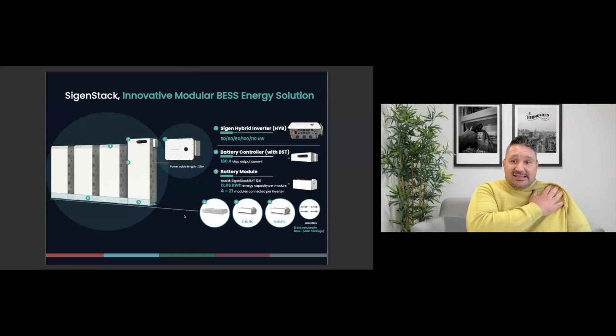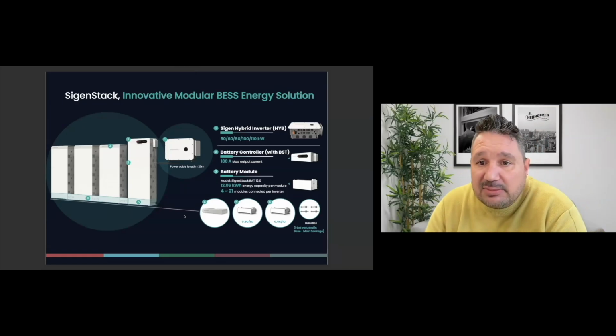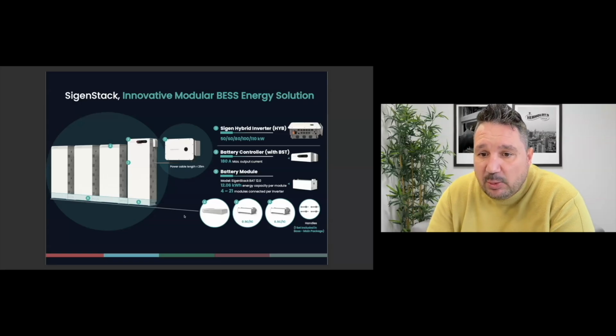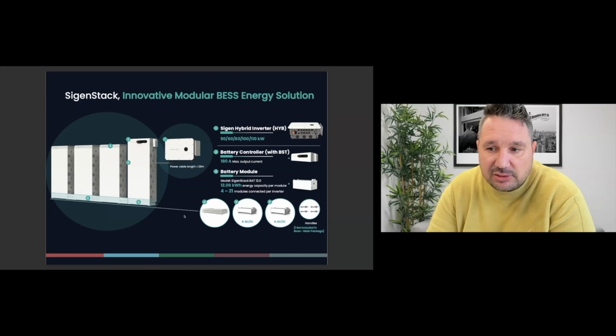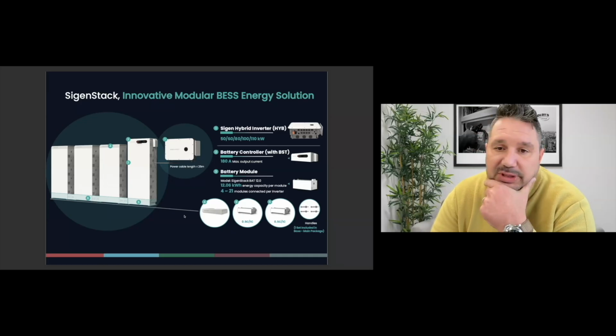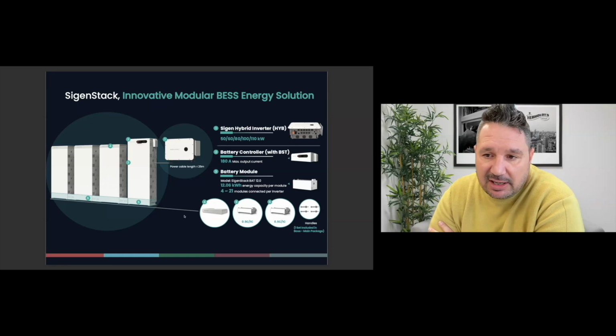SigenStack, which is the C&I and industrial solution, now comes between a 50, 60, 80, 100, and 110 kilowatt hybrid inverter with a battery stack that can stack up to 240 kilowatt hours per unit, which can give you a 1C or half C type design. Each one of these battery modules is 12 kilowatt hours. They stack on top of each other and then connect to the inverter. Up to 300 kilowatts, you can parallel. If you need anything up to 10 megawatts, there is a gateway that then handles all of the switchover. Also, if you tie into medium voltage, this can be done via a transformer.